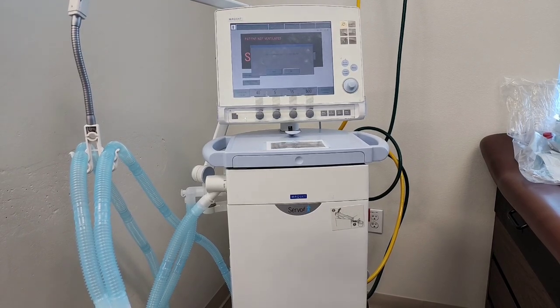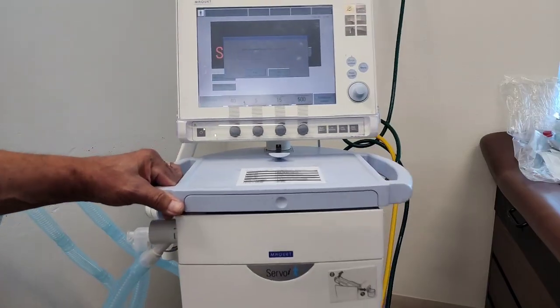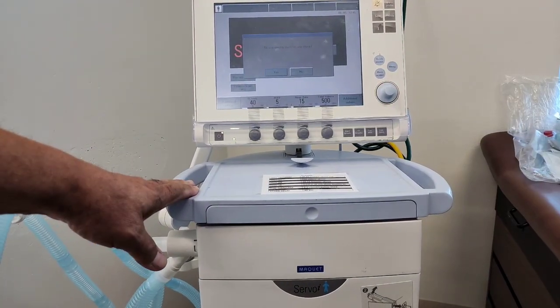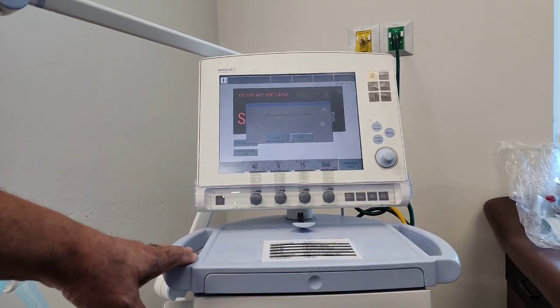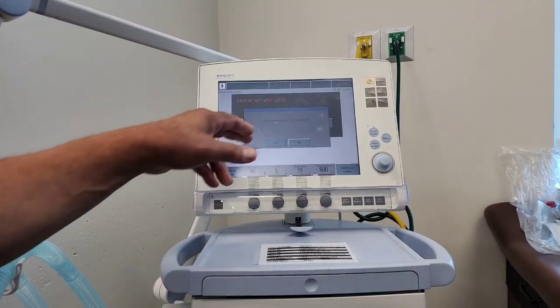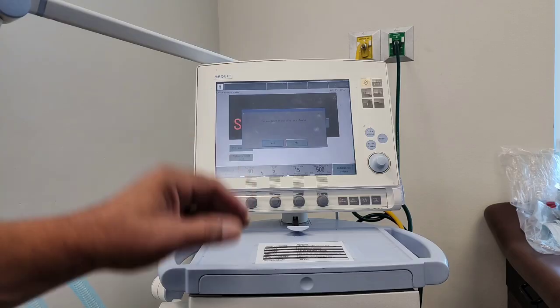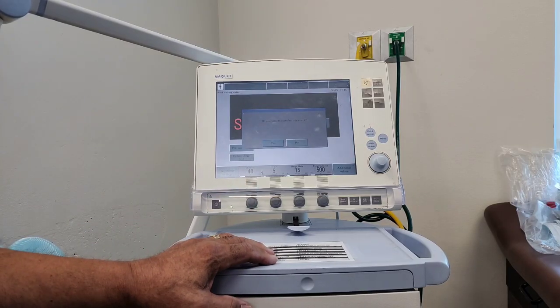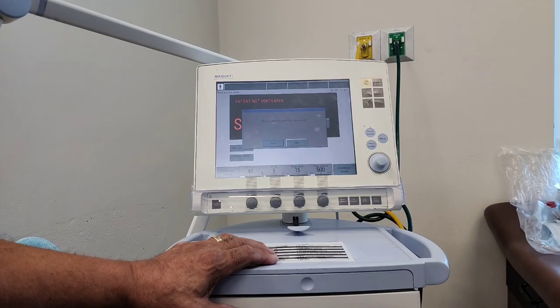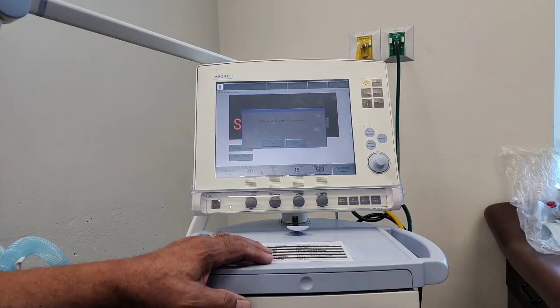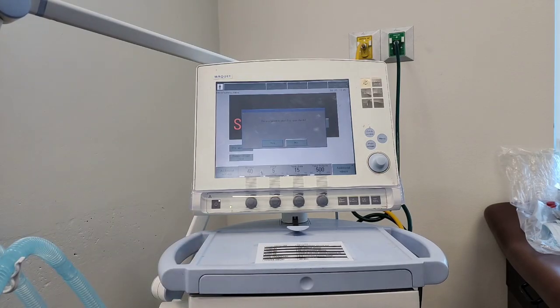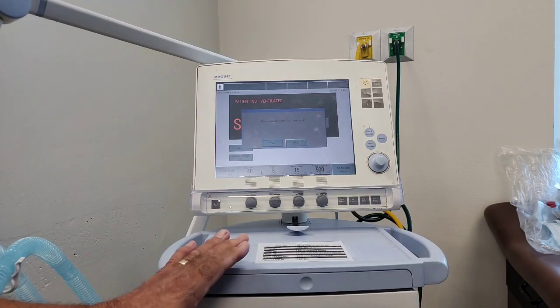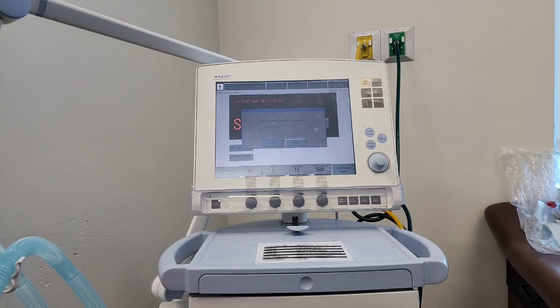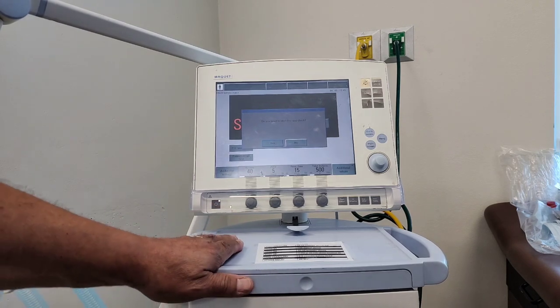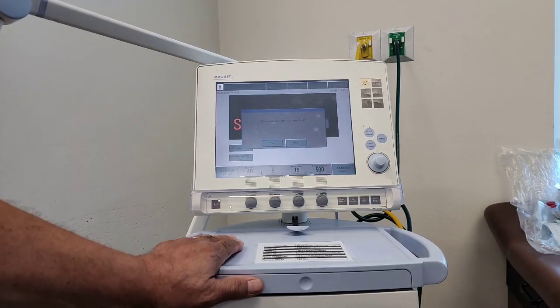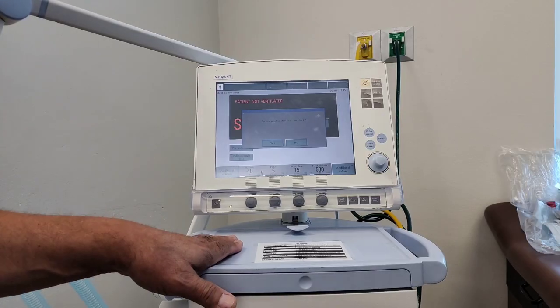And it automatically goes into standby mode. I think I'm going to move it a little closer and see if we can see. Okay, so right now it says, do you want to start a pre-use check? The only ventilator that we could do a check would be the PB980. These other ones here, there's just some parts of them, like this one here, the O2 sensor, which is inside here, is not functional, so that one will alarm all the time, so it will fail the system test, so we're not going to do that.